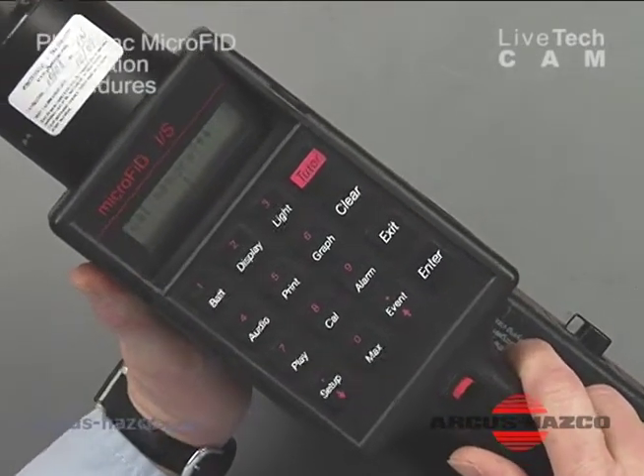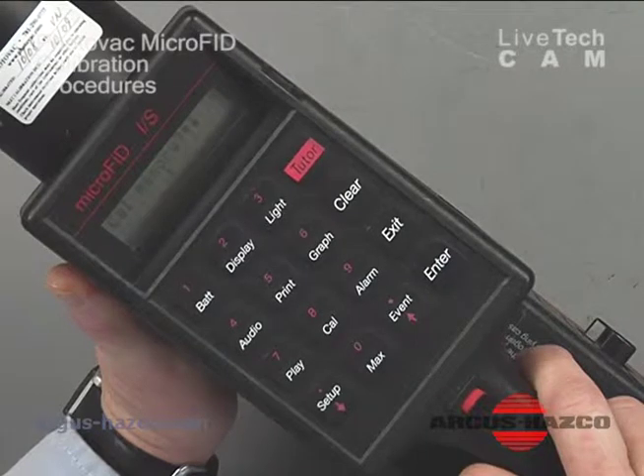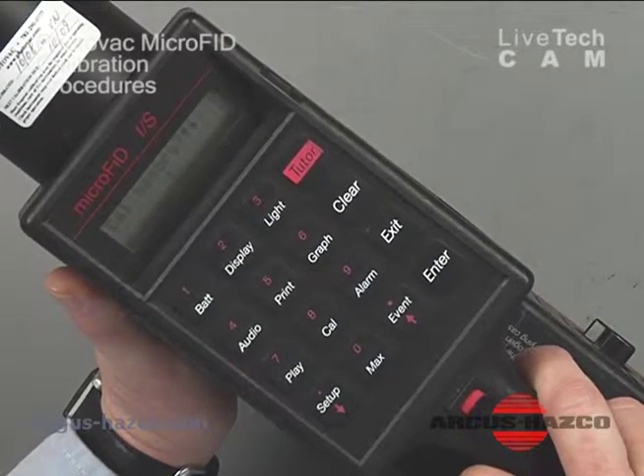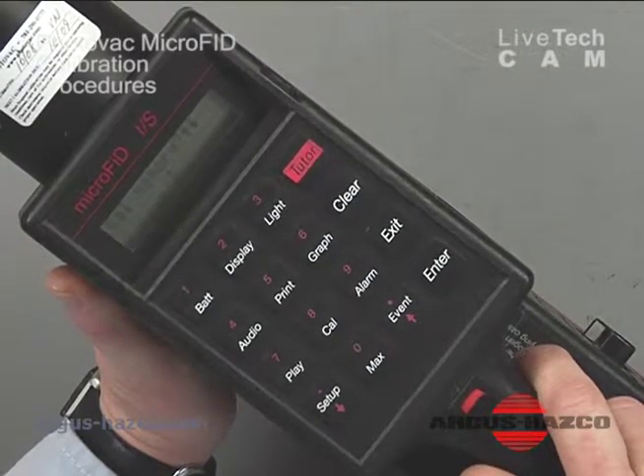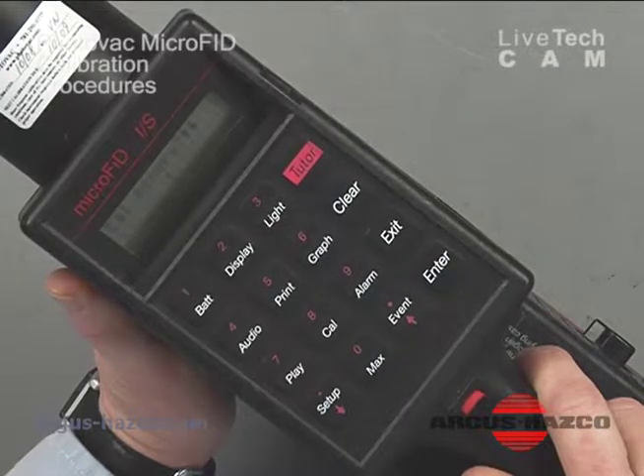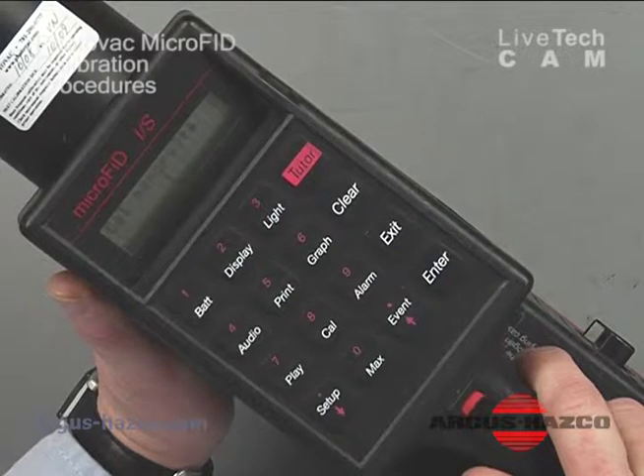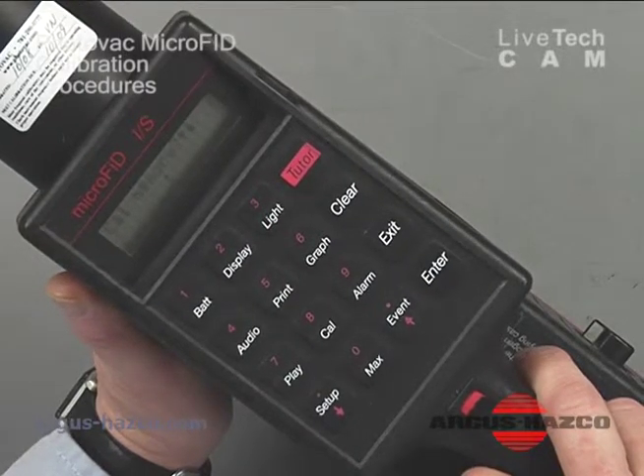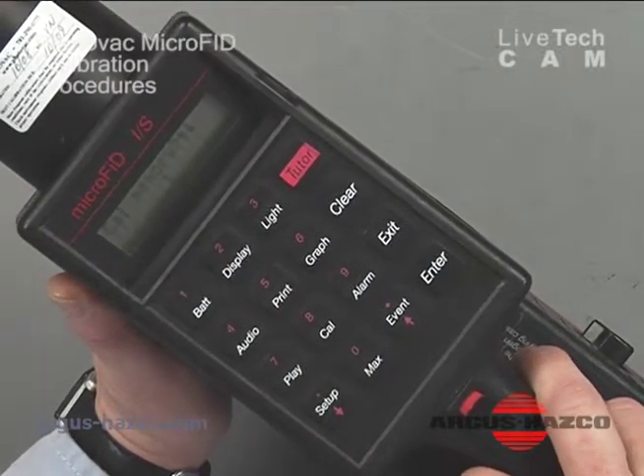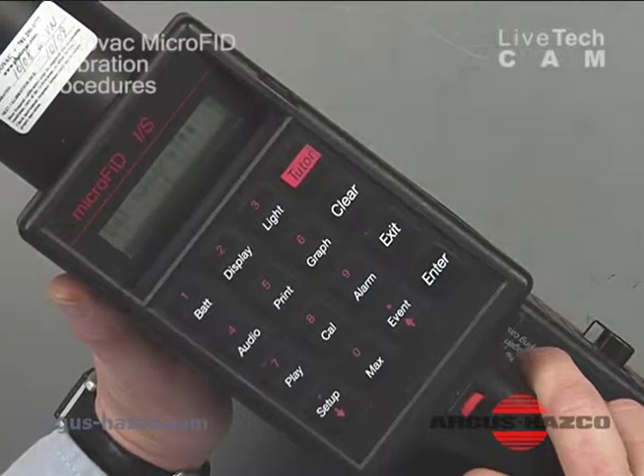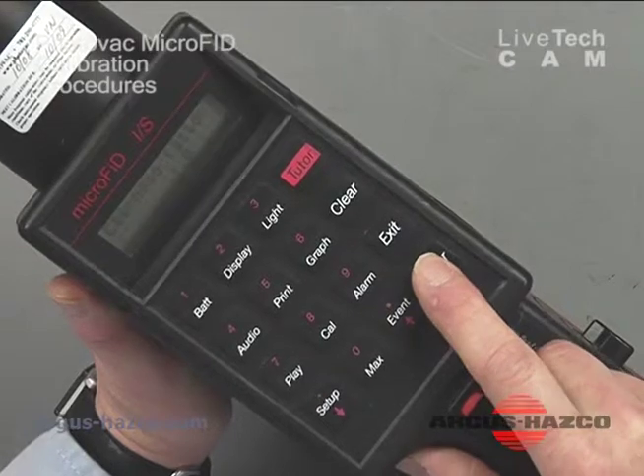And on our screen, the first thing that pops up is cal memory. The unit has 10 different memories. We always select calibration memory number 1. These different memories you can select for different calibration values or different calibration gases. We go ahead and select our cal memory number 1, and we will go ahead and calibrate to methane. So go ahead and press your enter key.